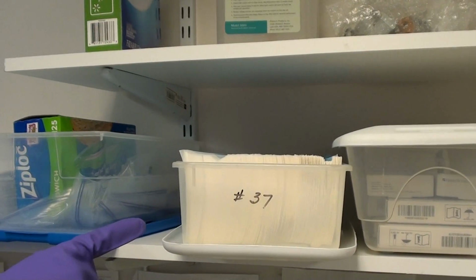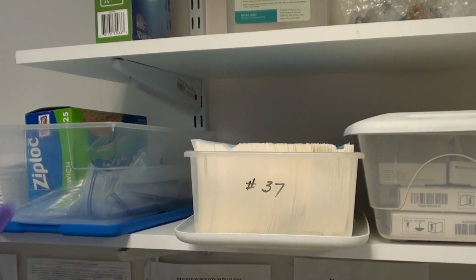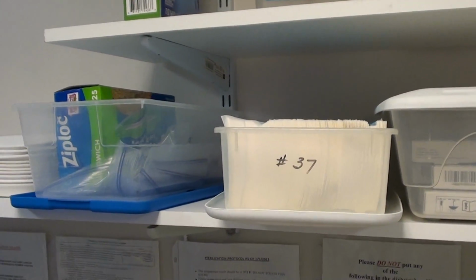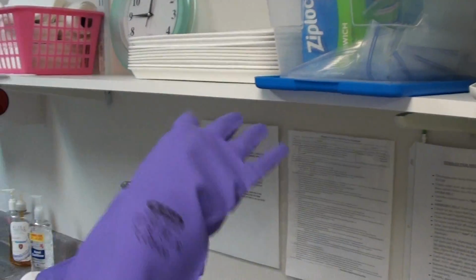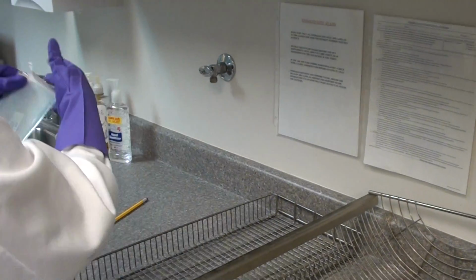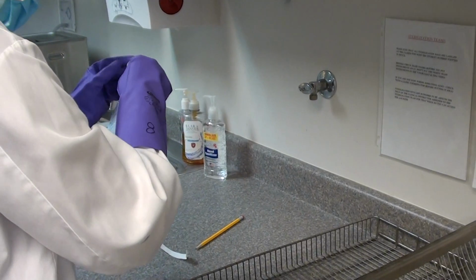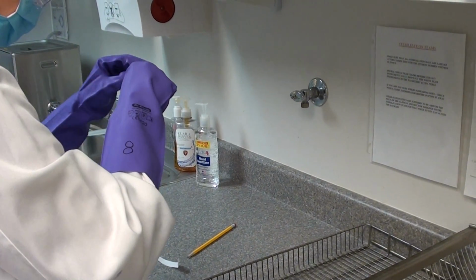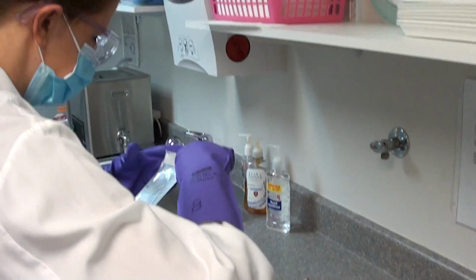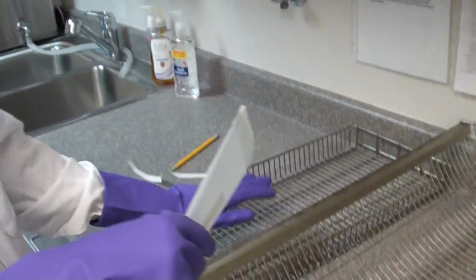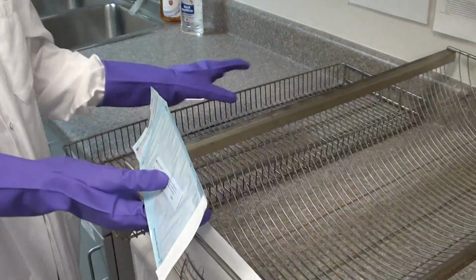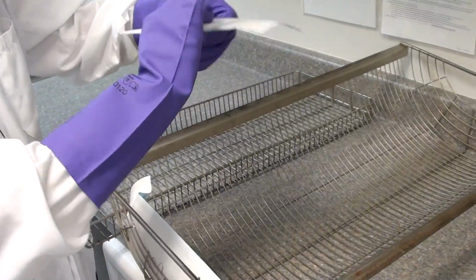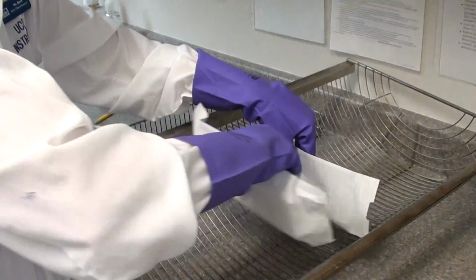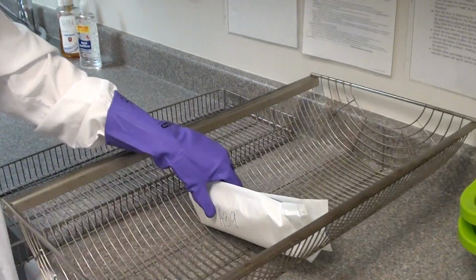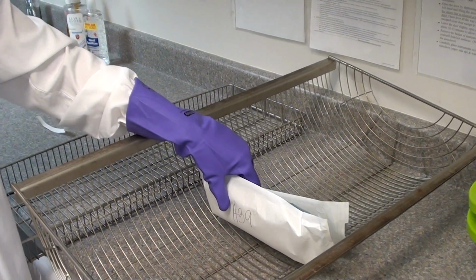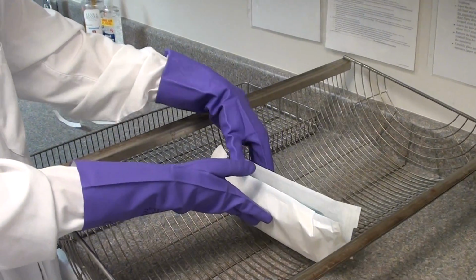And then one of the bags here is labeled dirty, so don't touch this one with clean hands. Clean hands, and then you'll put it in. You will seal it. And then in each separate rack that you have, you'll put one in the center. So pretend like this was full. I put it in the center because that's where steam is most likely to hit. It will be the hardest place to sterilize, so we want to make sure that it does.